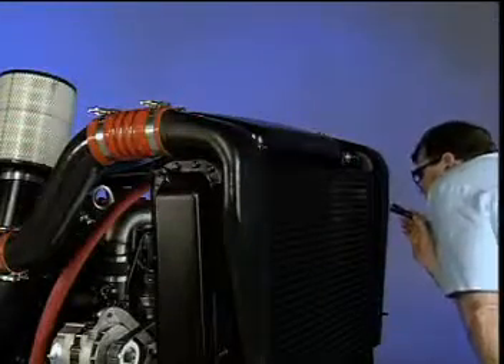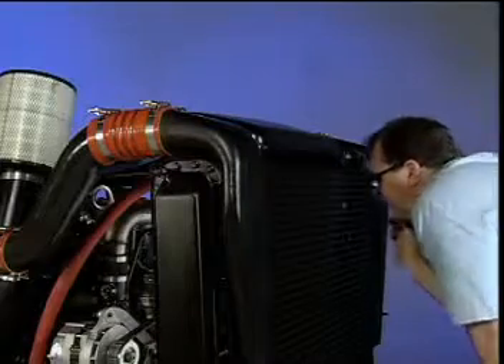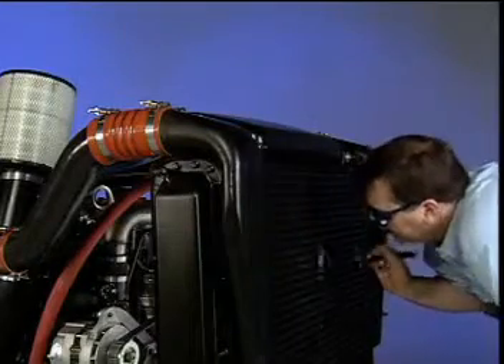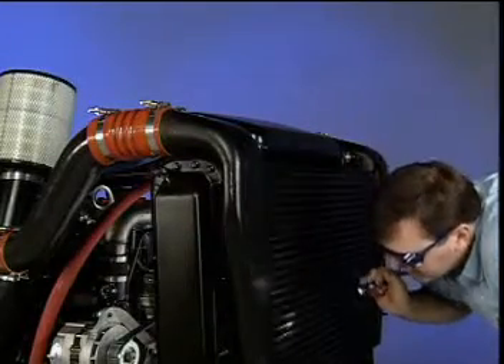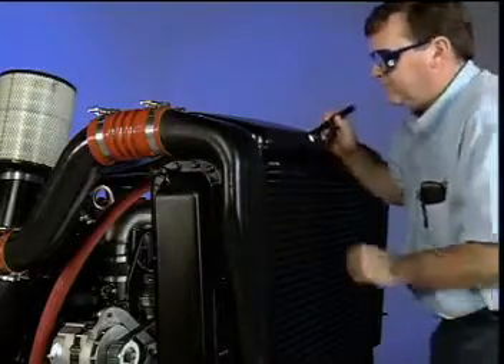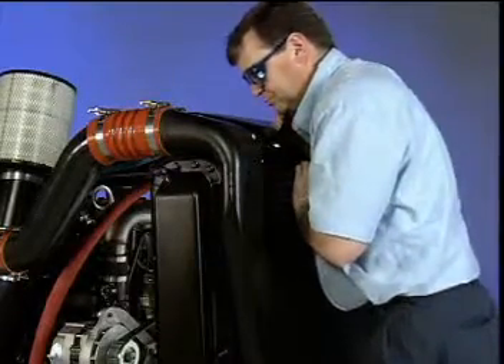If the temperature differential is greater than the specifications, check the charge air cooler for dirt and debris on the fins and clean them as necessary. Then, check between the charge air cooler and radiator for debris.